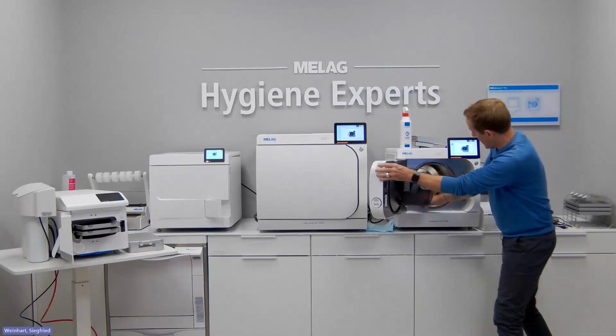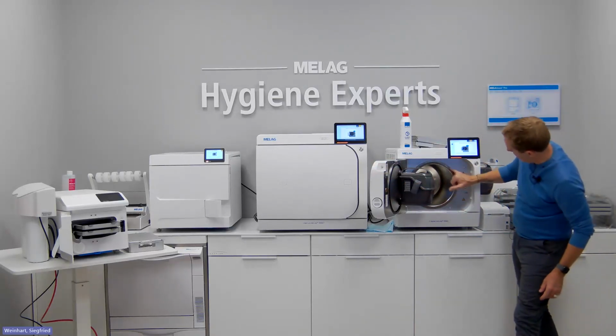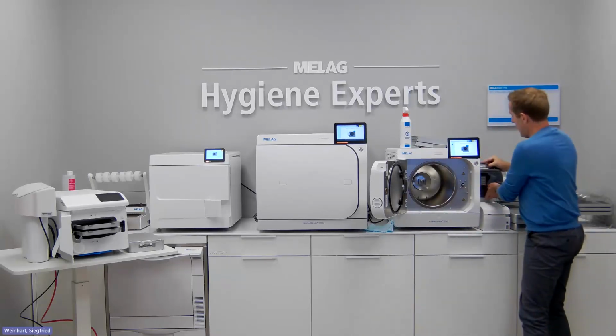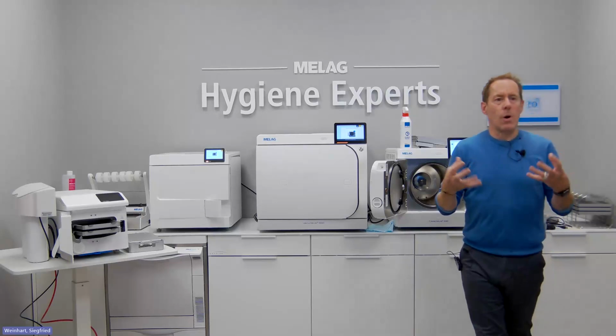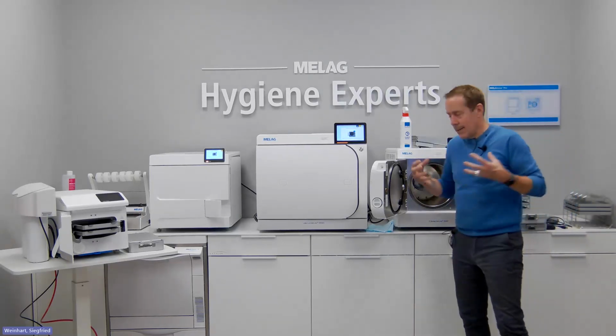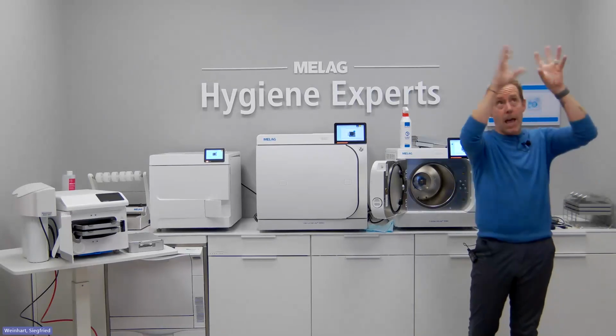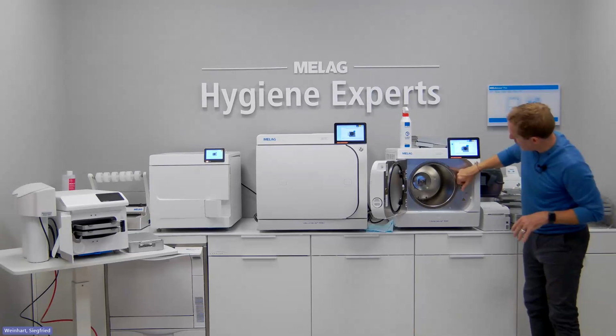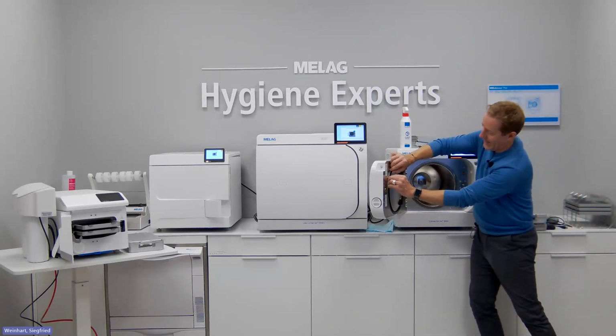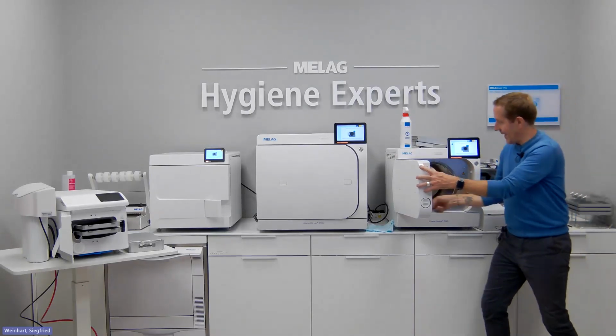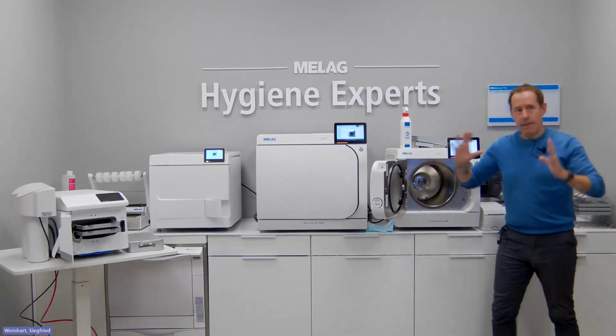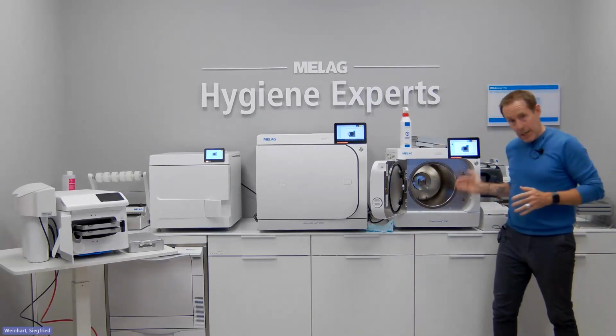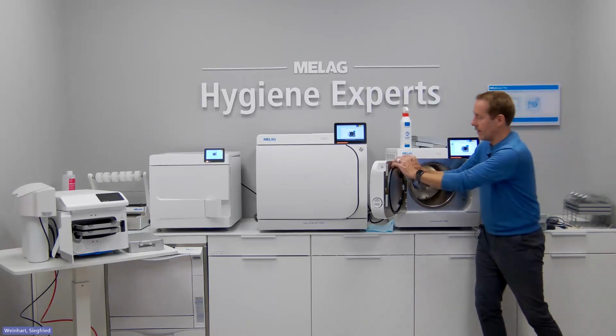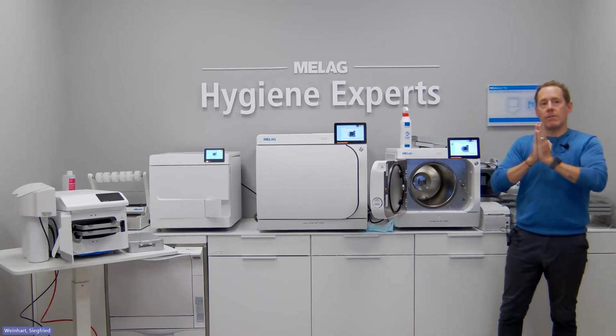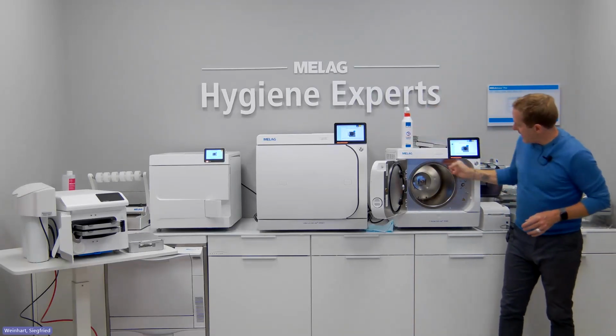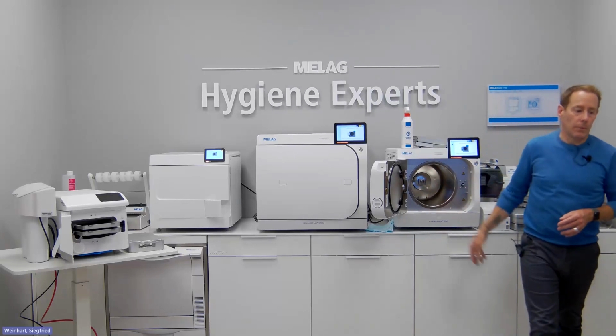Remember, you're not just doing the chamber, you're doing all around this door seal. This metal bit can sometimes get debris in it, particularly if your decon room is quite small and stuffy. There can be a lot of airborne particles and debris in there. Little bits can get inside this door area, and the door gasket here, this rubber seal, if there's debris on it, it might inhibit the gasket from creating a nice tight seal. That's especially important with vacuum autoclaves, which rely on a tight seal. So once a week, clean all this area, the door gasket, and the chamber, then throw the cloth away afterwards.